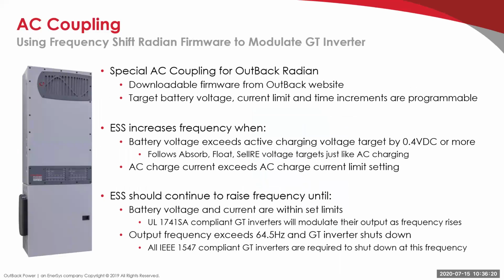Okay, so the Radian uses a frequency shift technique. We used to use something called a blackout relay to protect the battery. If too much charge was coming from the grid-dependent inverter, we just cut off the connection. So now we use a technique called frequency shift. To get this to work, we have some downloadable firmware from our Outback website. You download that firmware and load it onto the Radian inverter using our system controller, our Mate3 system controller. You program it just the same way you normally would, with the battery voltage, current limit, and for how much time.